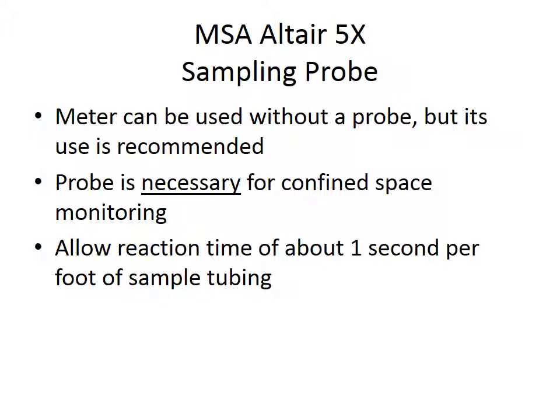Okay, why I say it's recommended, even though it works without the probe, is just think, in your investigation, if you're dealing with this situation in a building, about what the meter looks like with that probe attached, with that sampling cord and the probe. If you have to get up into a ceiling space or some other confined area, it just gives you that extra reach to get into those areas. When you have the sampling probe attached, MSA says you need to allow for a reaction time of about 1 second per foot of sample tubing.